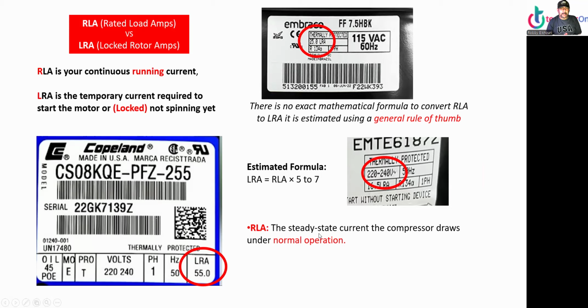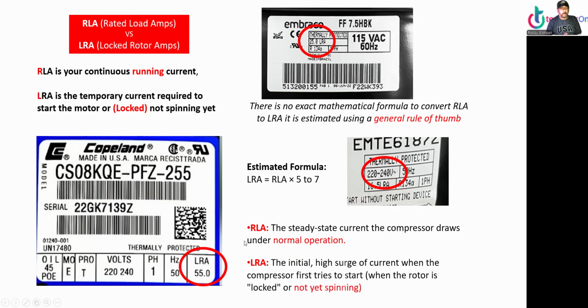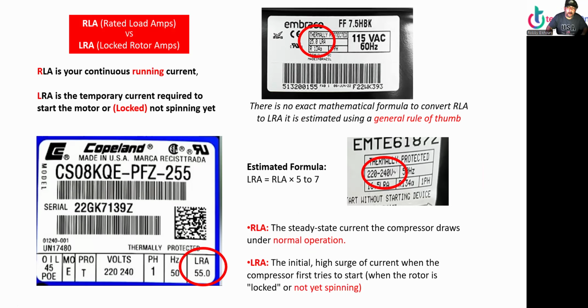The rated load amp is the steady current of the compressor under normal conditions. And locked rotor amp is the initial high surge current on the compressor prior to start, when the rotor is locked. All right, let me pause here for a second. Look at the small screen. So this is locked. This is spinning. All righty. Now, it takes 7 times harder to start. It takes 7 times harder to do this than to move. It's very important. That's what we had to learn in school, believe it or not.